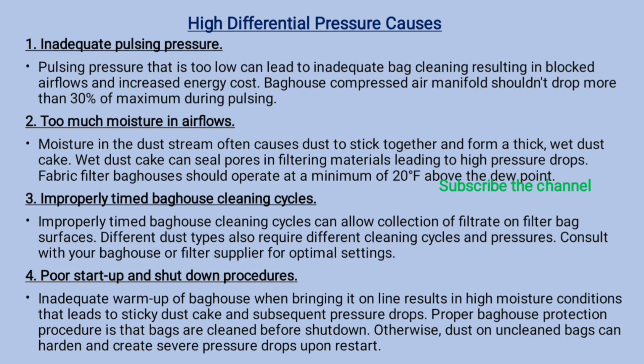The baghouse compressed air manifold shouldn't drop more than 30% of the maximum during pulsing. Point number 2: Too much moisture in air flows. Moisture in the dust stream often causes dust to stick together and form a thick, wet dust cake. Wet dust cake can seal pores in filtering materials, leading to high pressure drops. Fabric filter baghouses should operate at a minimum of 20 degrees Fahrenheit above the dew point.